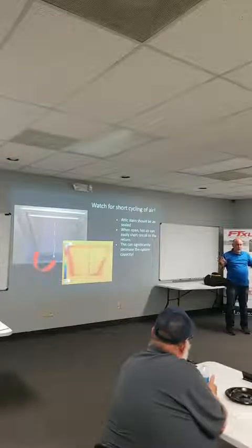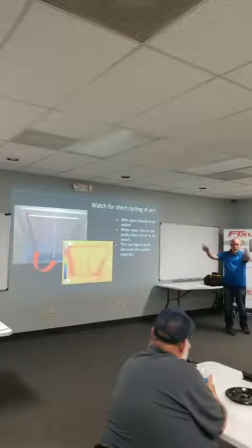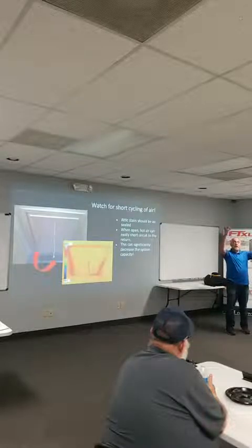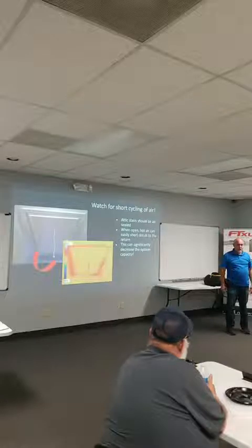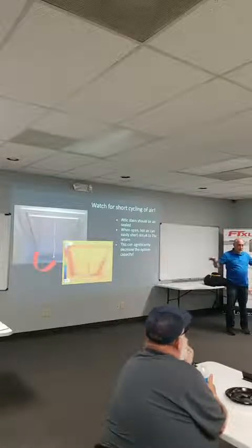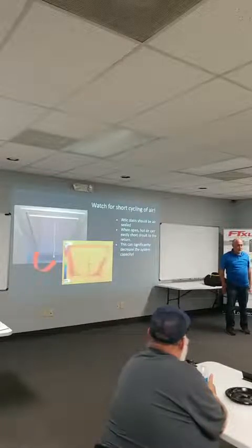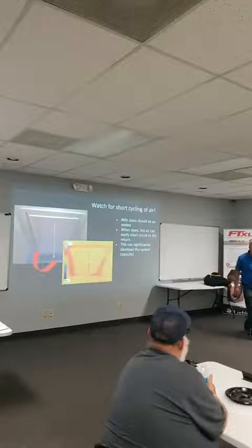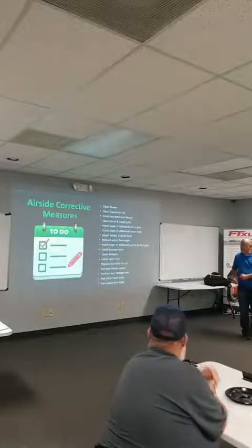But I got my particulates down to nothing in my room, in my space, because now I'm actually creating an environment where I can blow air out and return it back to those returns. Otherwise, like in here, the only thing that's going up in the returns is what happens to be in the air, whatever particles are in the air. You cannot suck dust particles to that return. You have to create an area of entrainment to get those back. So it's just one of the challenges we have in the system.